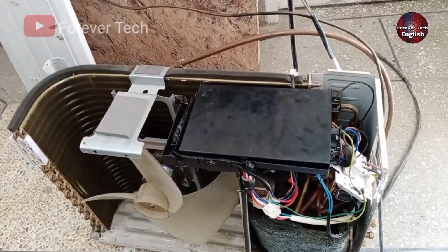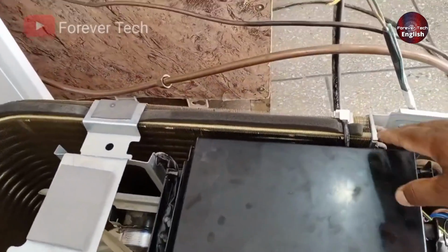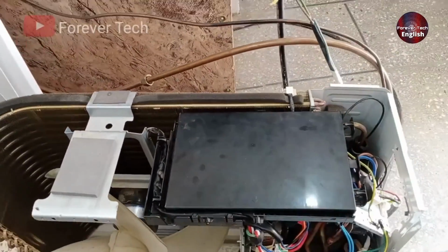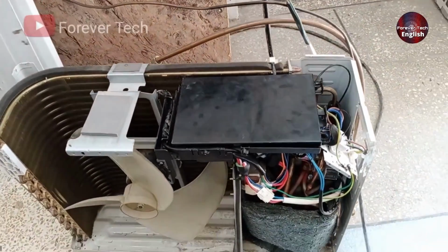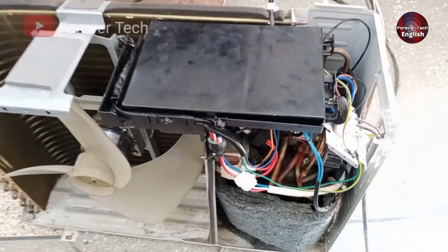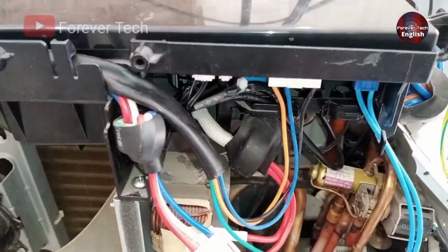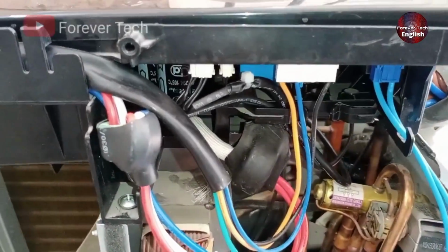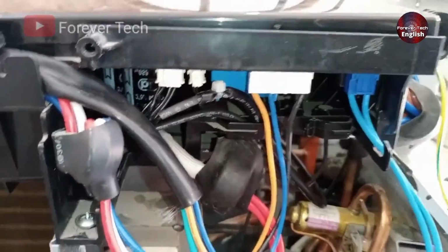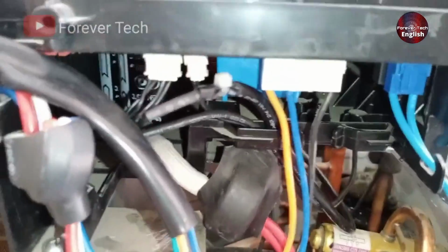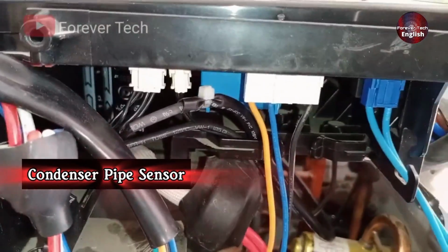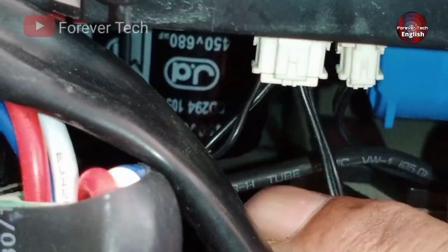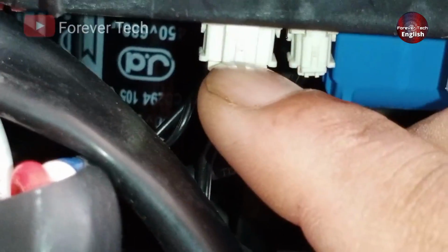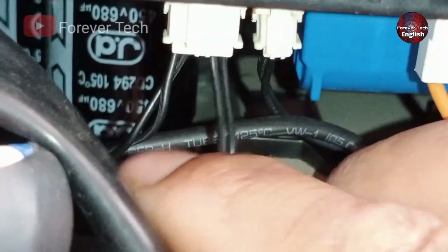If the condenser gets too hot and overheats, there is a system in place to check whether it's overheating or cooling properly. Let me show you that system so you can determine the current condition of the condenser and the state of the liquid going to the indoor unit. Here, you can see there's a sensor installed called the condenser pipe sensor. As you can see, there are 2 sensors connected to the same connector here. The one on the left side is the condenser pipe sensor.